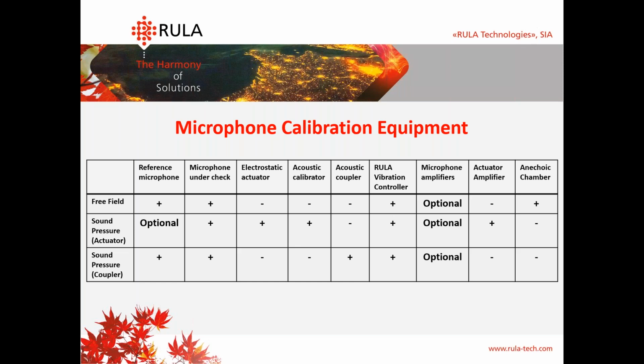Yes, it's more complicated, but you can get really good results using this. The precision is really high. And if you have a regular calibration lab, you can use an actuator or coupler based on sound pressure methods. Using the actuator, you need your microphone under check. The reference microphone is optional, and in that case, you need to have an electrostatic actuator and an acoustic calibrator. In case you have a reference microphone, you don't need a reference acoustic calibrator. So you can enter the sound pressure level in the software, and in that case, you don't need a reference microphone.